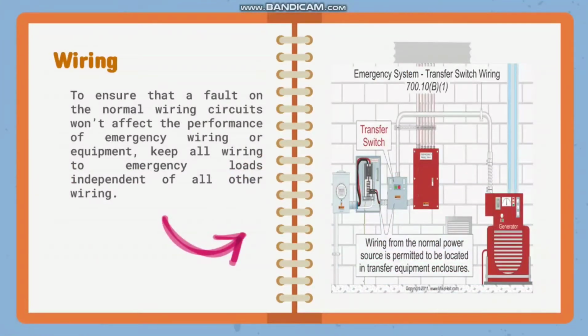To ensure that a fault on the normal wiring circuits won't affect the performance of emergency wiring or equipment, keep all wiring to emergency loads independent of all other wiring. Wiring from the normal power source is permitted to be located in transfer equipment enclosures.